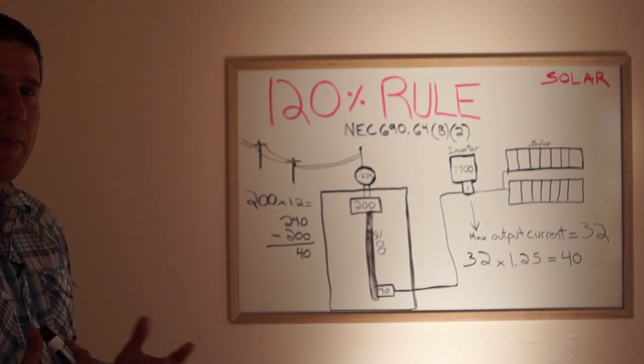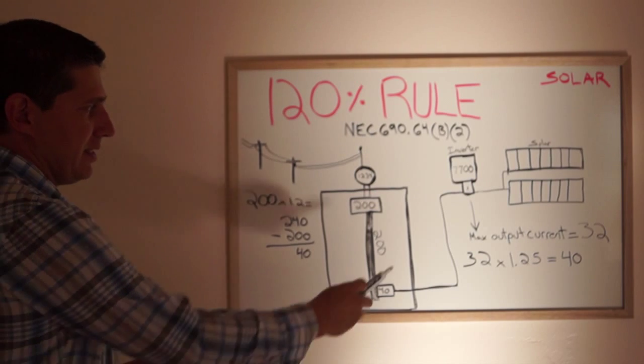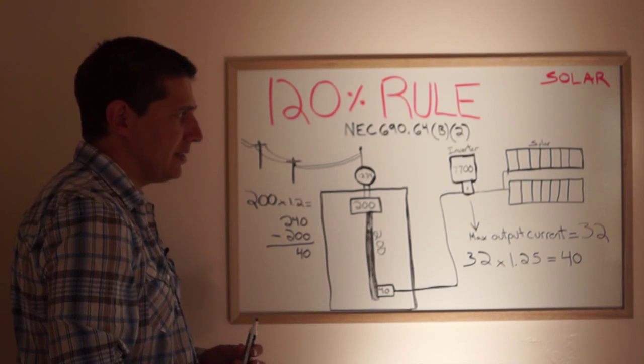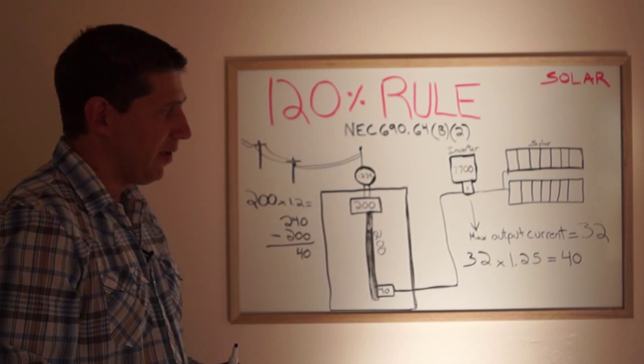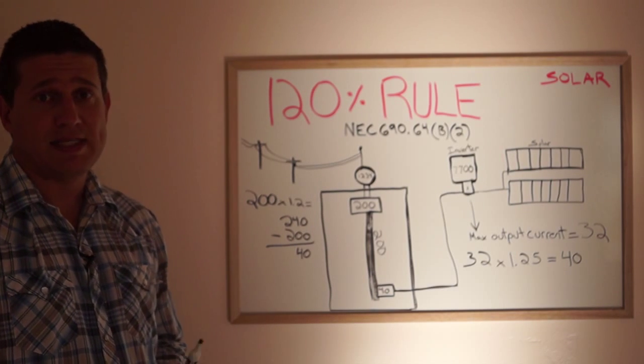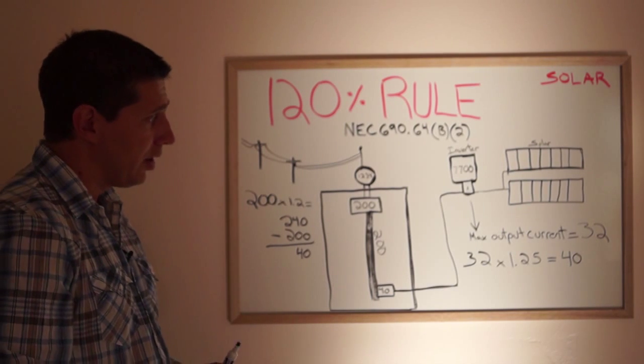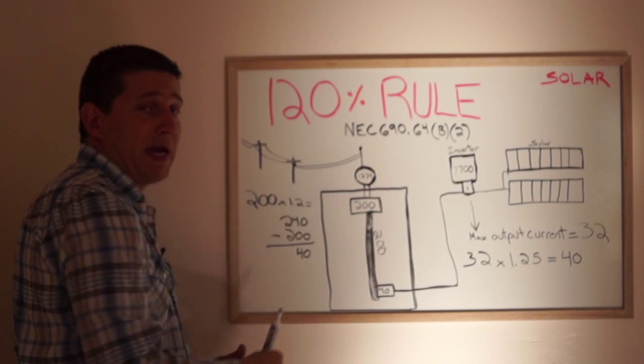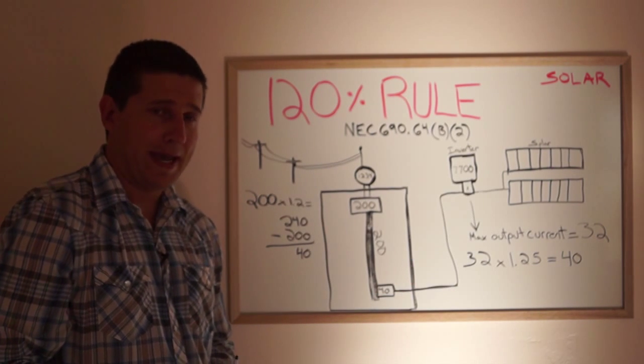Now what does that equate to? How big of a solar system? Well I've listed this out. The max system size we can put on here from the inverter is a 7700 watt inverter. That inverter on the spec sheet has a max output current of 32 amps.